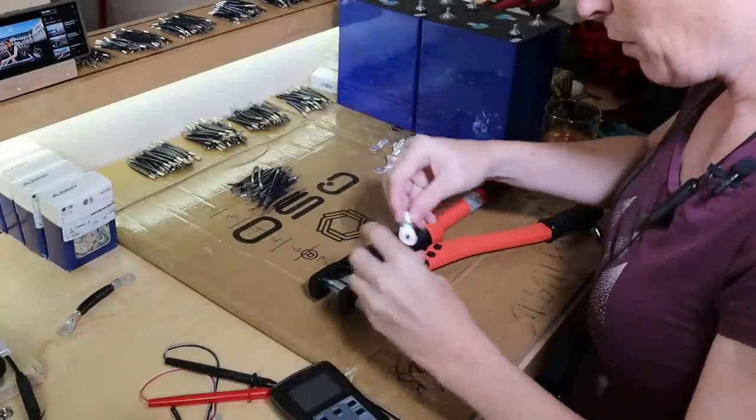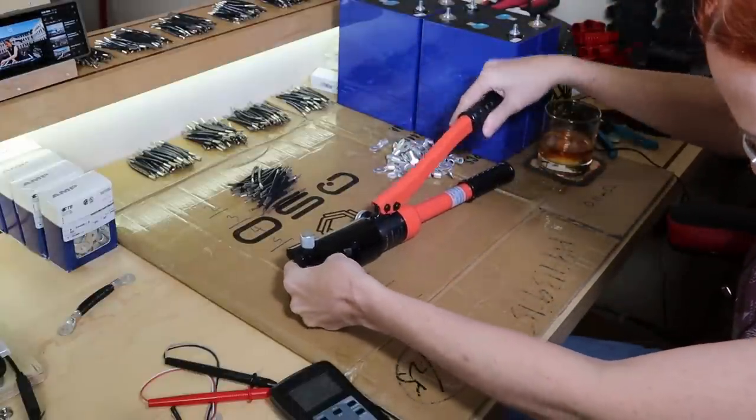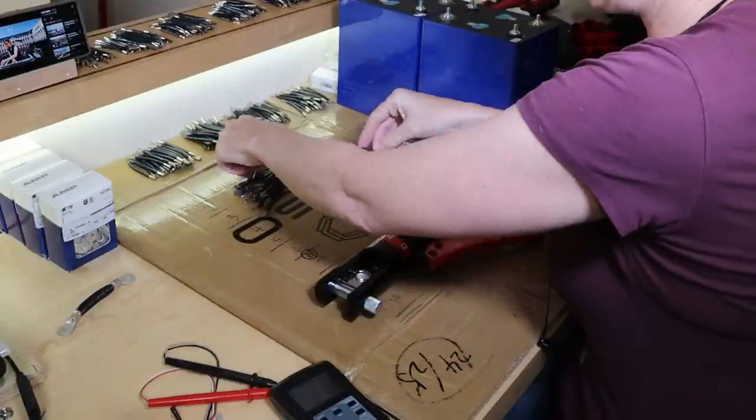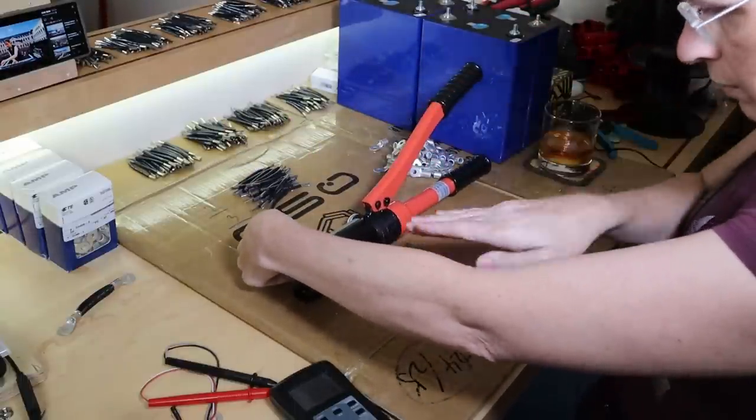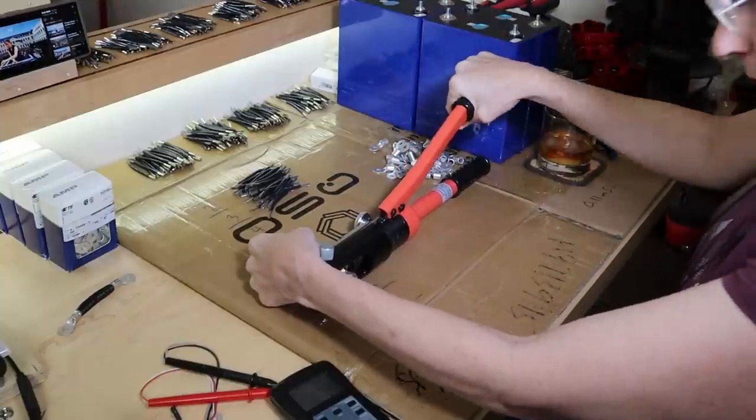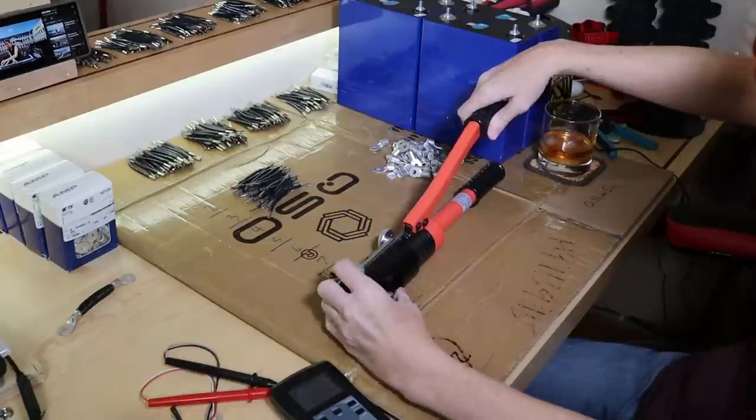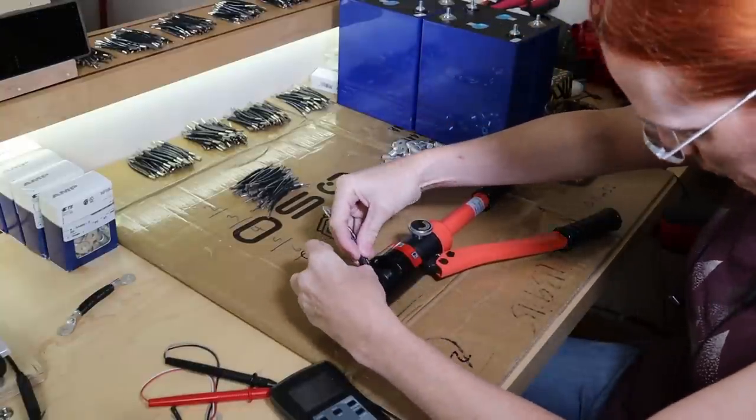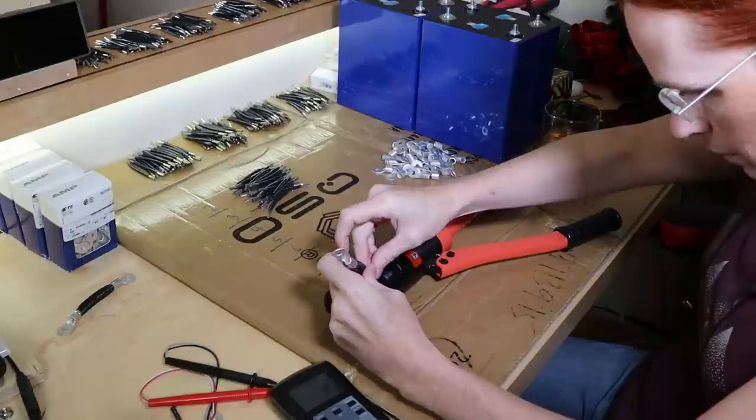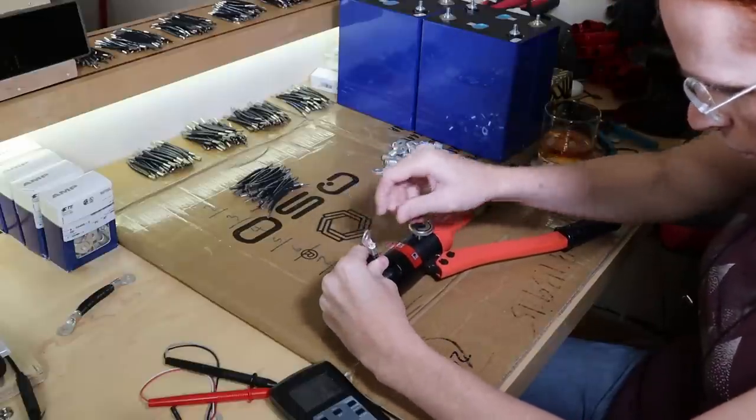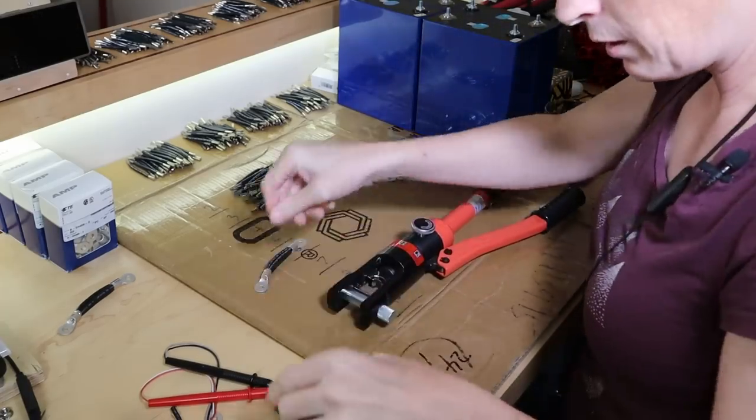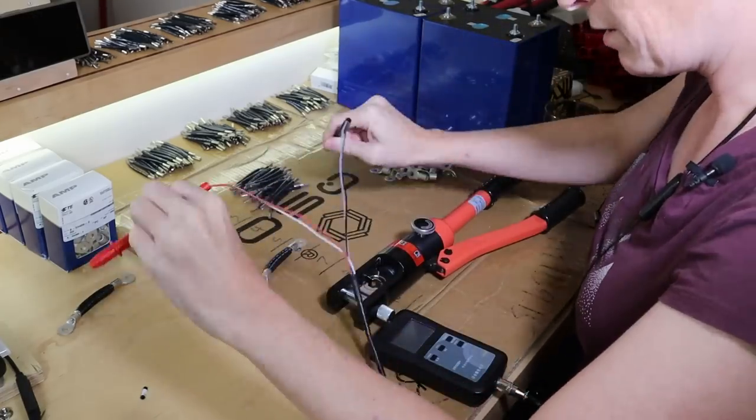Our number to beat is 0.1 milliohms. I think now I remember what I was doing was I was getting one started and then putting the wires in. It's starting to come back to me now. No strands. Lined up properly. Double crimp. Yeah, pre-mounting that definitely made life a lot easier. Come on. It'll all go in there. Get to know each other very well. That's two made. Let's see if we get 0.11 again. 0.11. Oh, that's consistent. And this is the process I'm going to repeat. So I'm going to put some music back on and just keep at it.